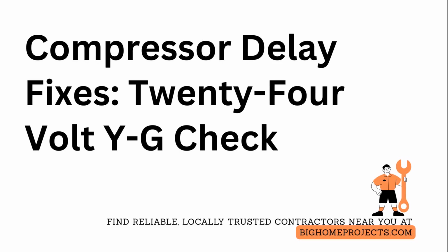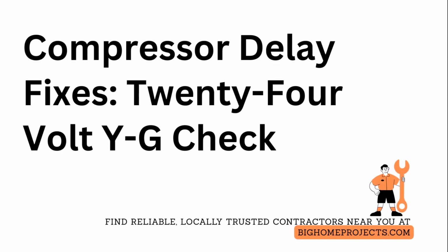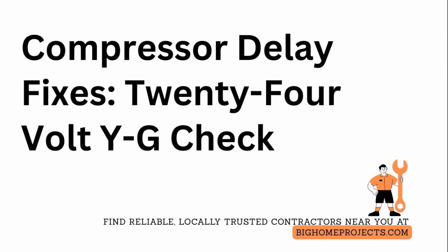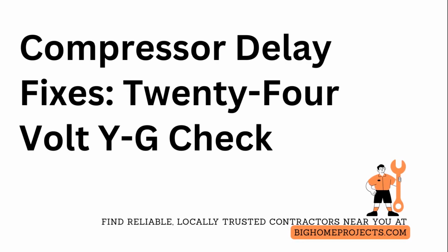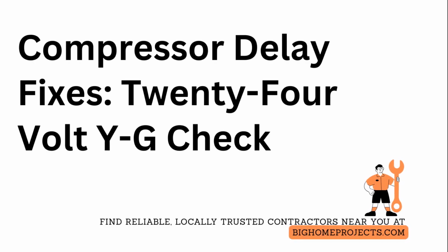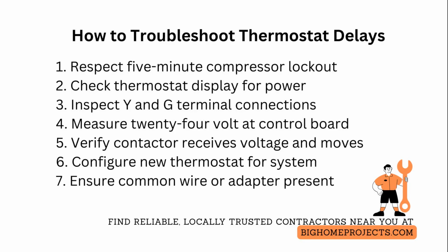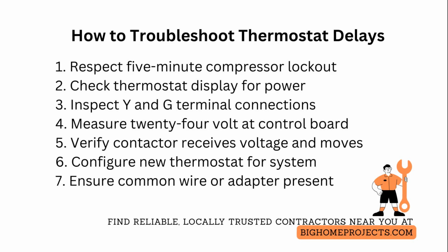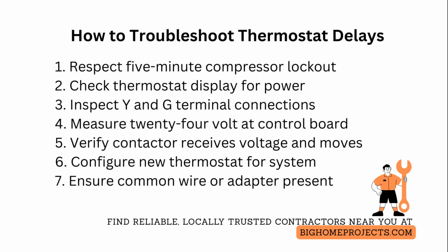Thermostat wiring and replacement. Check the 5-minute compressor delay, thermostat display behavior, and 24-volt signal paths before calling for service. When cooling does not start immediately after setting the thermostat, first respect the built-in compressor short cycle protection. Most systems enforce a timed lockout of roughly 5 minutes to protect the compressor, so do not try to force it by repeatedly changing settings.